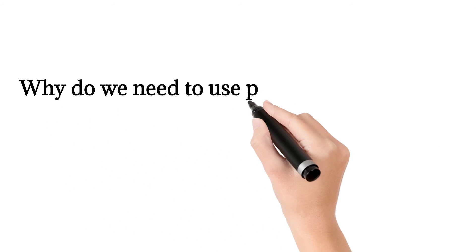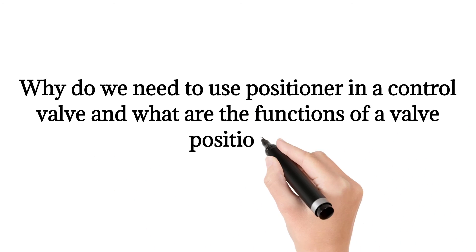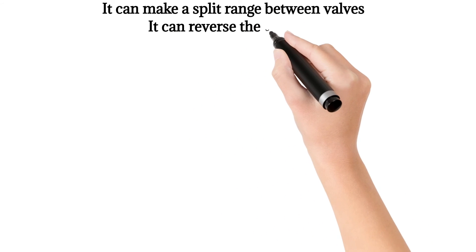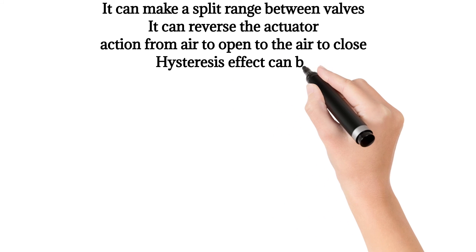Why do we need to use a positioner in a control valve and what are the functions of a valve positioner? It can make a split range between valves. It can reverse the actuator action from air to open to air to close. Hysteresis effect can be reduced.